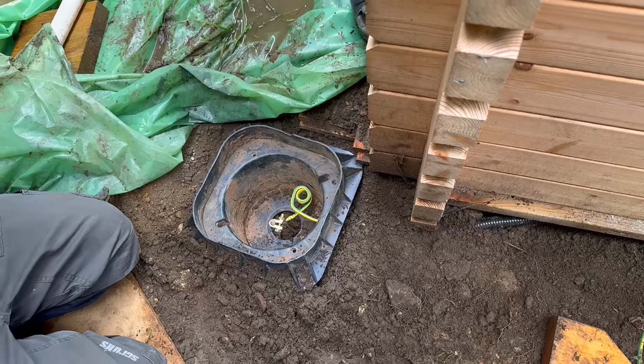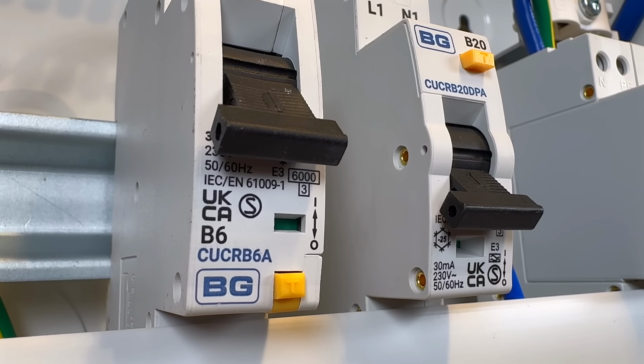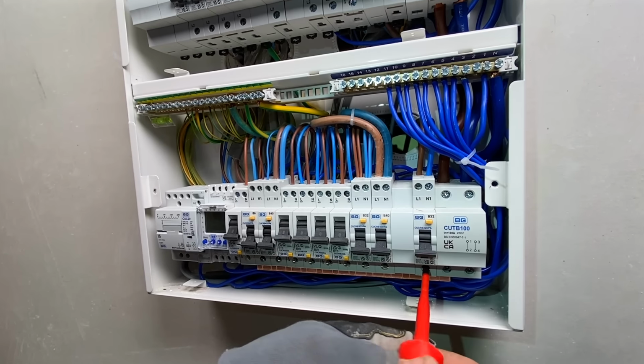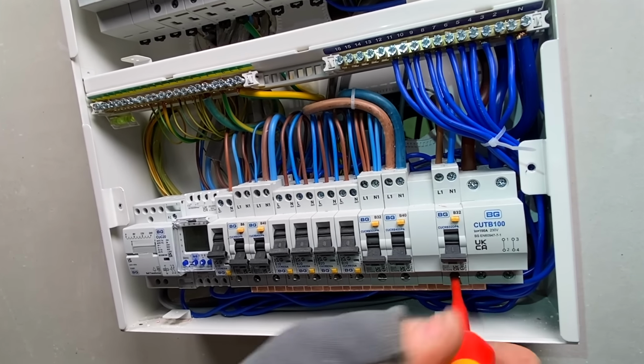And that distinction matters because the performance of the earth electrode is primarily linked to the RCD providing fault protection, not the devices providing additional protection at final circuits. Understanding which device does what job is essential when we start looking at test results and maximum permitted values. And we are going to come back to that later when we start putting real numbers against this installation.